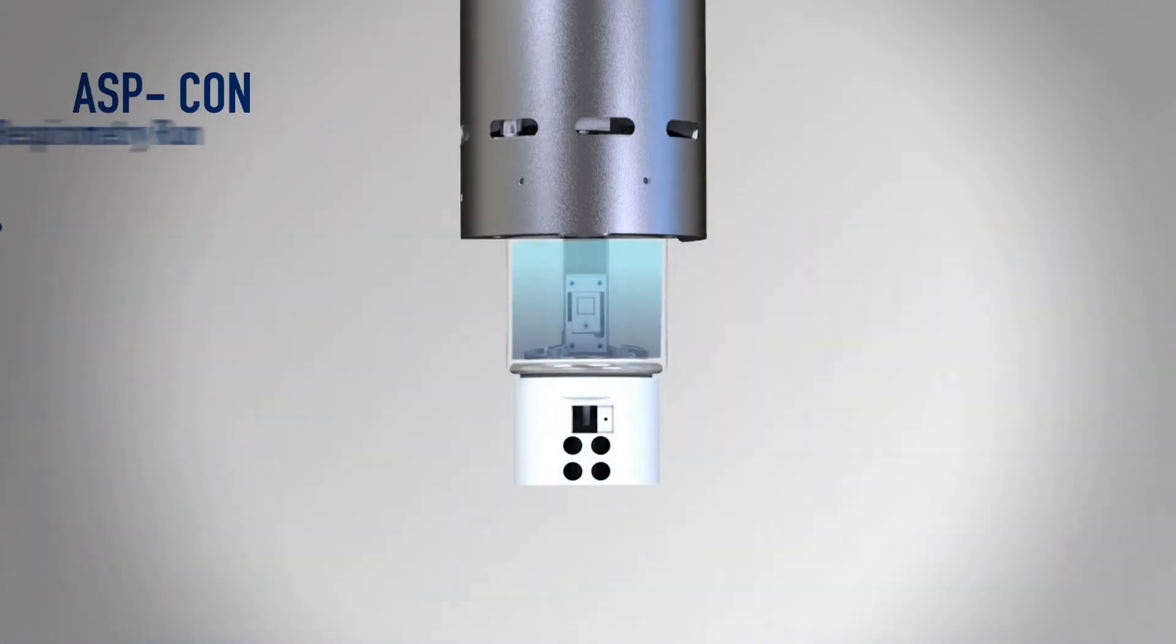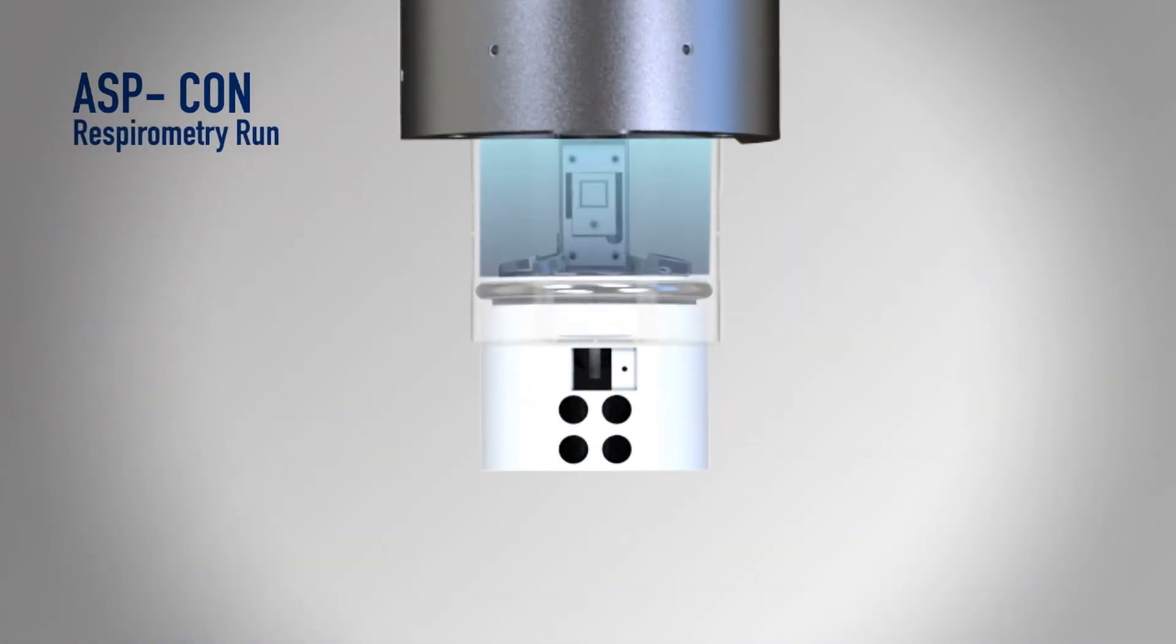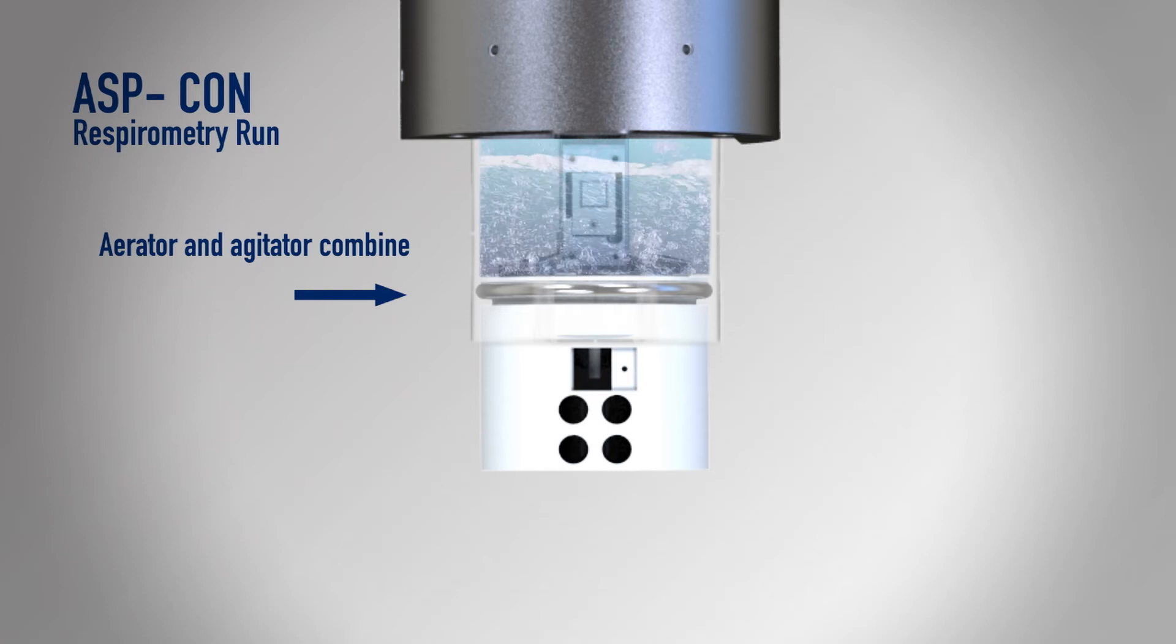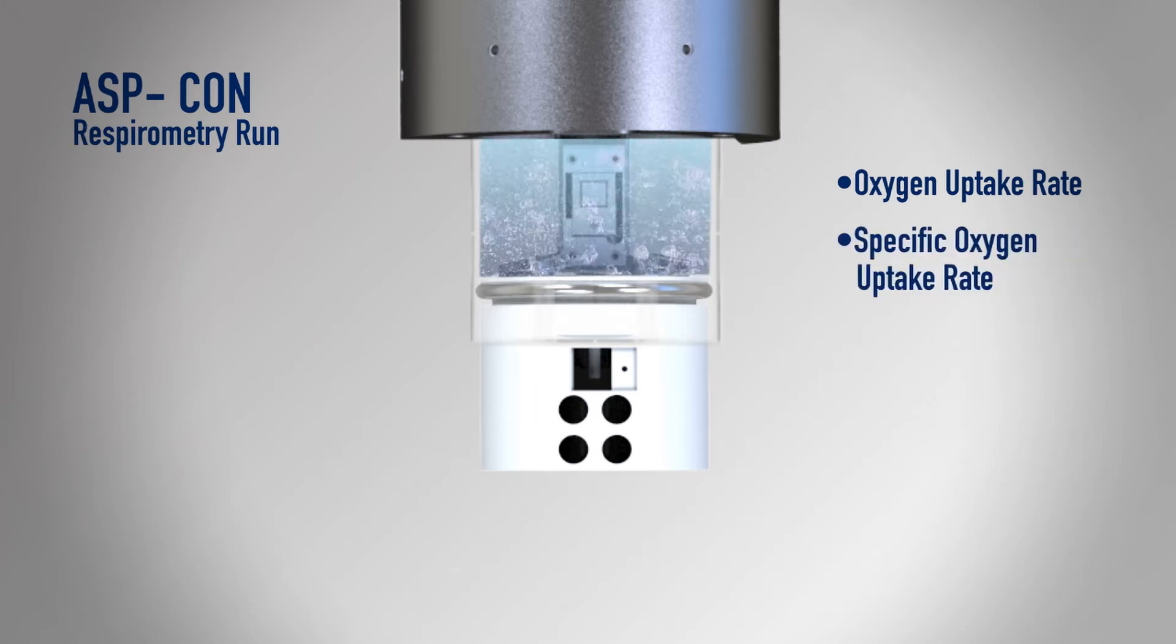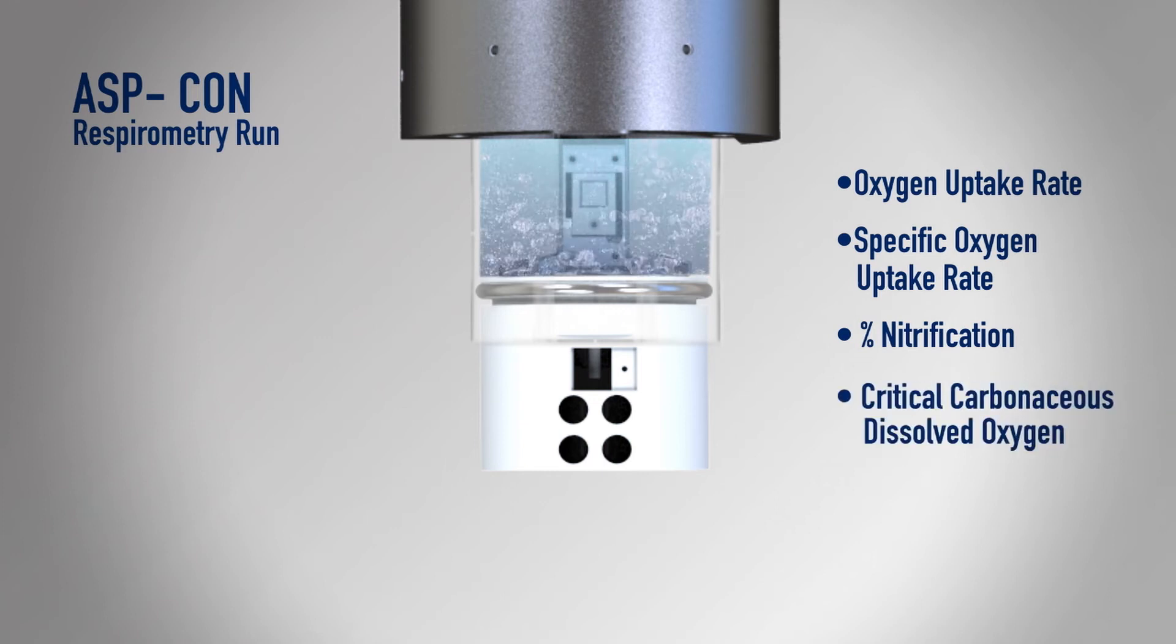The core then raises to cover the ingestion holes before the aerator and agitator combine to raise the dissolved oxygen level in the sample to allow for an effective respirometry run, including oxygen uptake rate, specific oxygen uptake rate, percentage for nitrification, critical carbonaceous dissolved oxygen and critical nitrification dissolved oxygen.